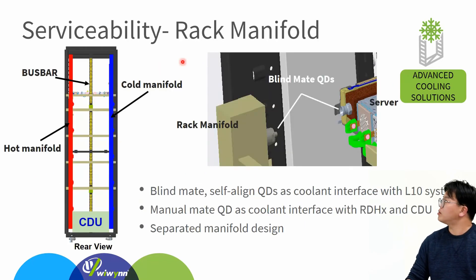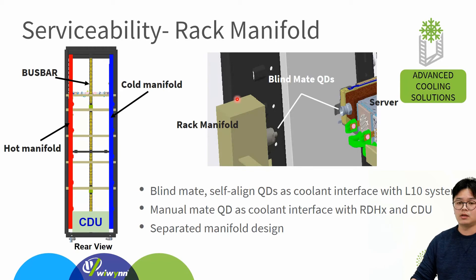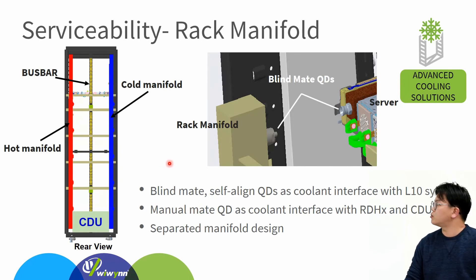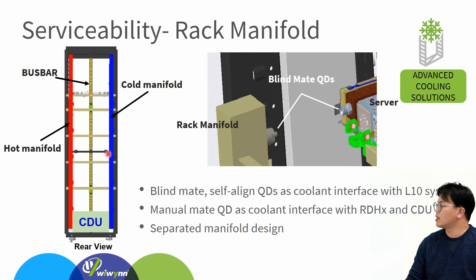For the Rack manifold, in order to maintain service from the coolant interface as currently used, we plan to use the blind mate self-align quick disconnector as the interface between the L10 system and the Rack manifold. For the CDU and Rack manifold connection, we prefer to use a manual quick disconnector to simplify the design. For the Rack manifold, we prefer to use two separate manifolds to balance the connection force, and we can get more flexibility for quick disconnector sizing to meet different system requirements.